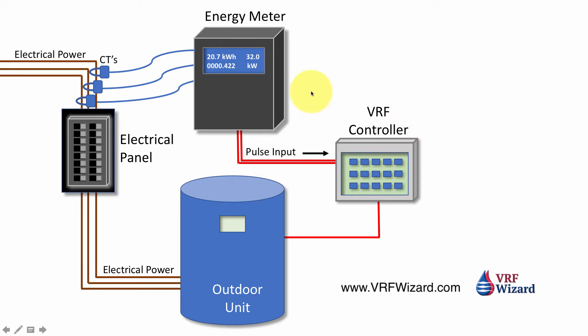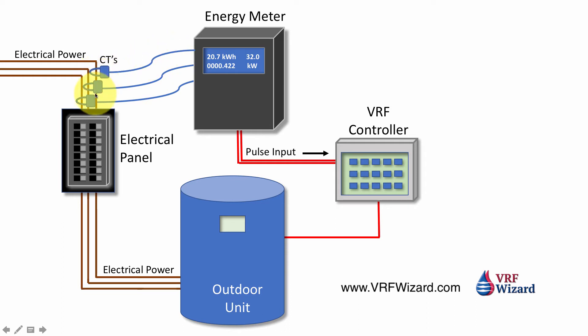One way is to tie in an energy meter which keeps track of the power consumed by attaching CTs — current transformers — connected to the energy meter around the wires feeding the outdoor unit. It's important that wherever you put these CTs, no other equipment is being fed off those power lines. It should be just feeding the outdoor unit you want to monitor.